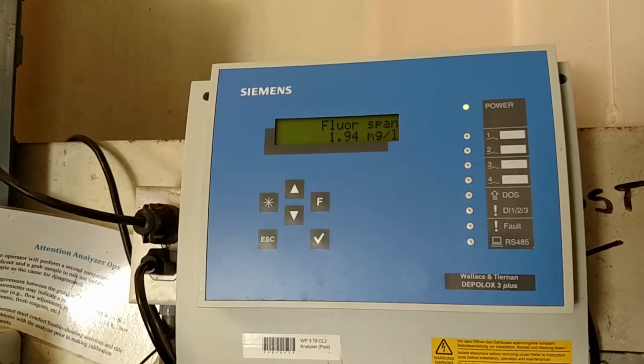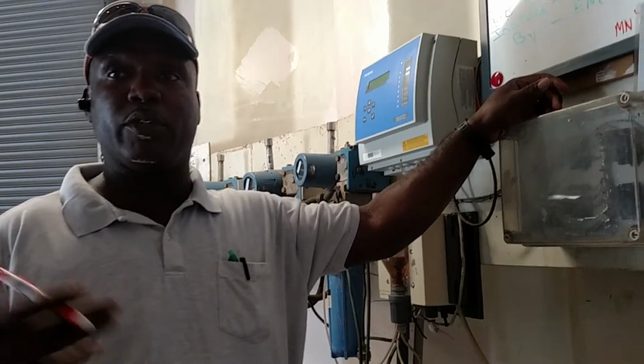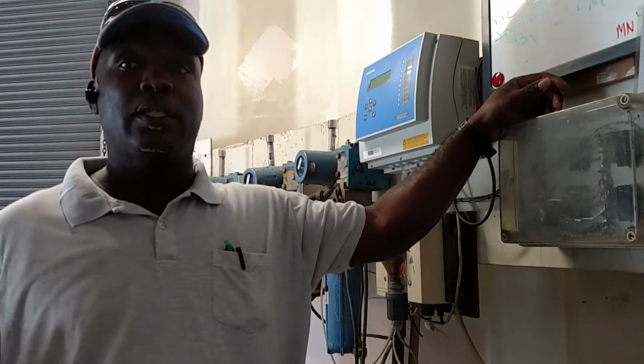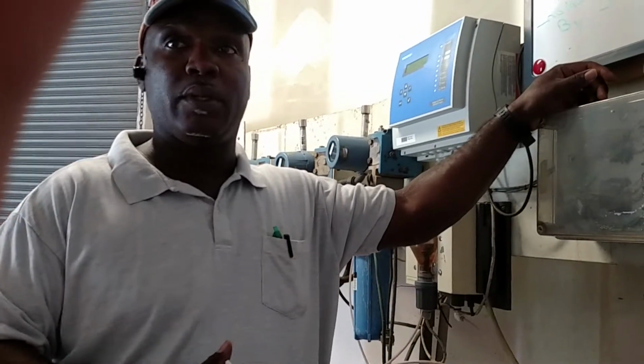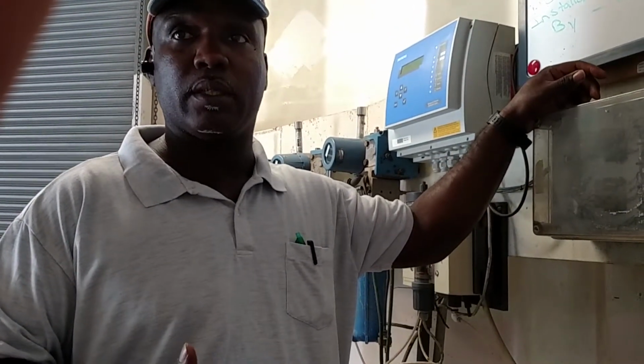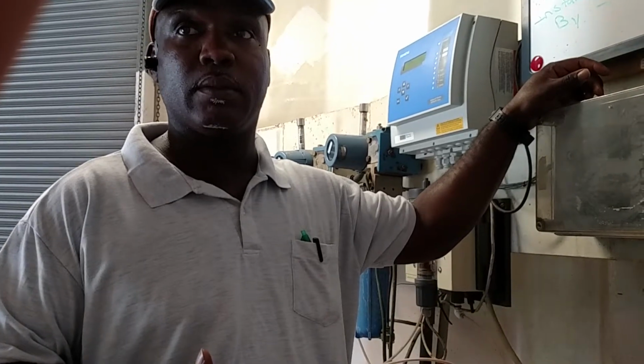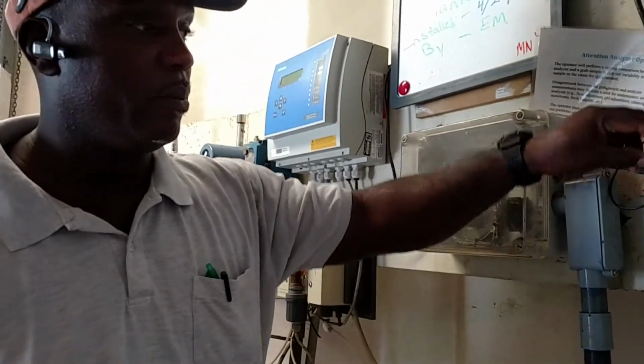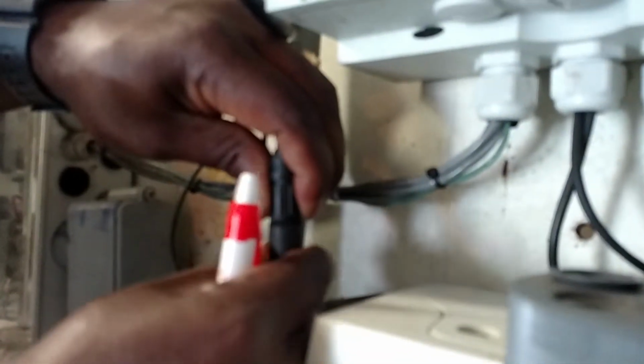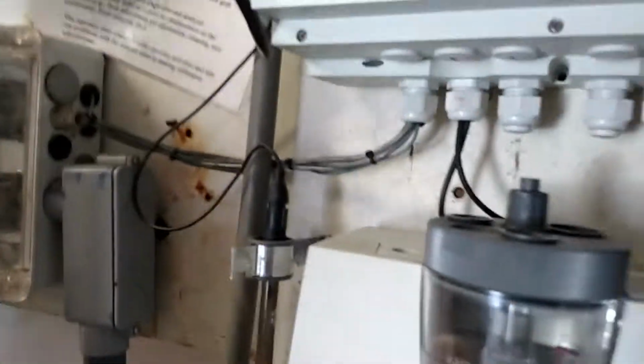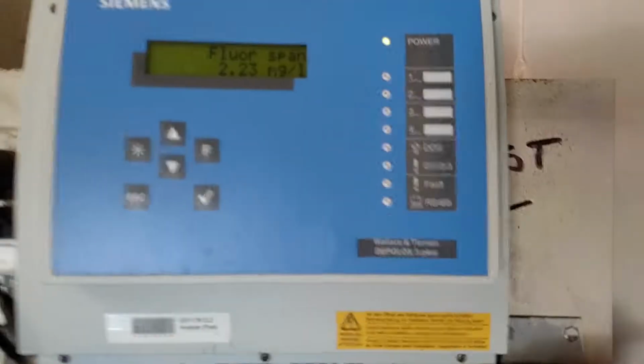Now, the pre is not as critical as the post. So you can do without the pre if you have to. Say if you go somewhere and the post is not acting right, but your pre is acting right, and you don't have an extra probe, take it off the pre and put it onto the post. And you already know how to take these loose, correct? I actually have not done it. All right, well, we're still calibrating, but basically what you would do is come here, hold the knotted part, and just unscrew. Oh, okay. And it just comes right off. And then you just put a new one on there and move on. Go through the calibration process with a new one?